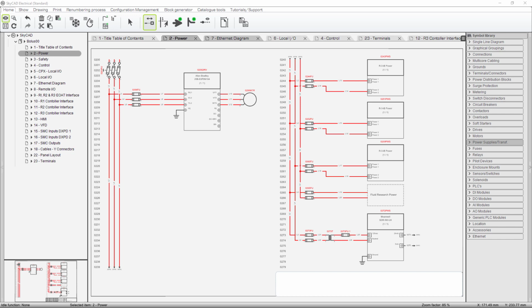The last device on this page is the power supply, 24 volt DC power supply. There's actually two devices there. The first one is the transformer. So we got two fuses feeding the primary of the transformer. Now a transformer transforms one voltage level to another voltage level. In this case it's a step down. I'm stepping down from 240 down to 115 or 120. Now I don't show it, but the actual transformer has more than 4 terminals. So it allows you to make the proper connections for primary and secondary for the ratio that you want. Voltage in, voltage out, etc. And this particular transformer has fuses mounted right on the transformer. There's an advantage to that because it saves panel space. And believe me, this transformer is bigger than that power supply. A lot bigger. Because you've got a lot of power going through it, and you've got the fuses mounted on it.